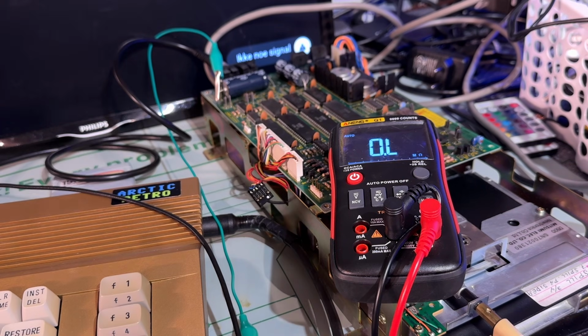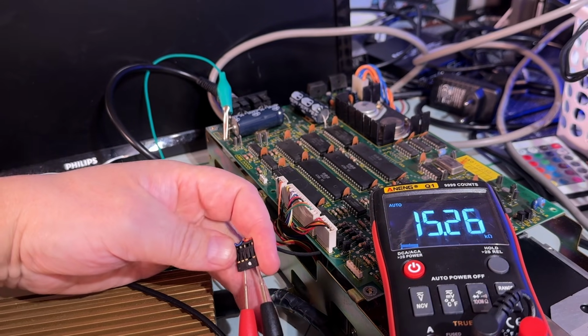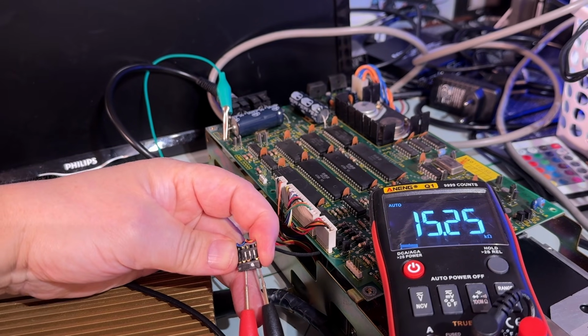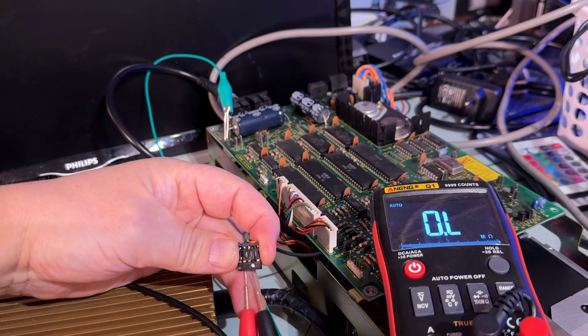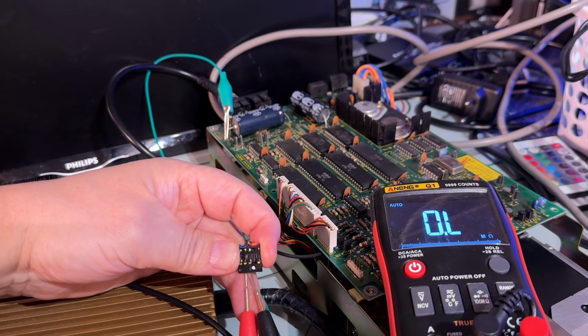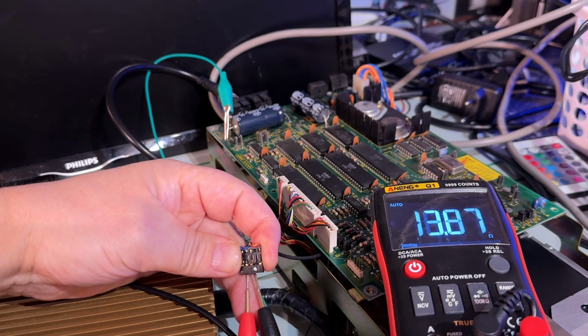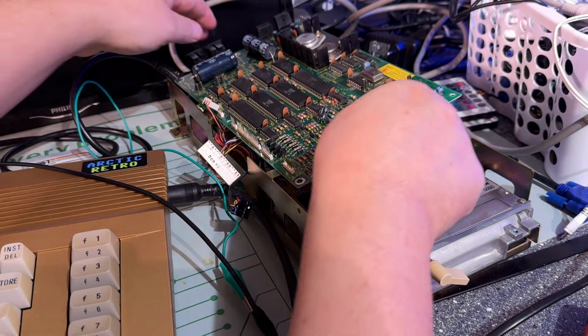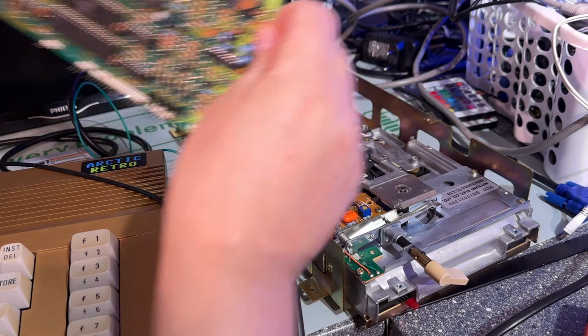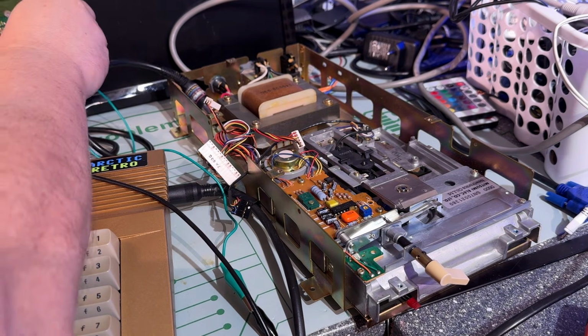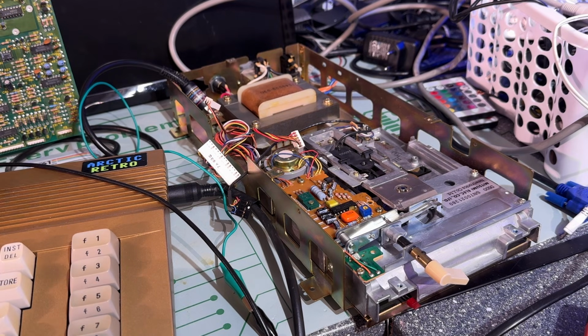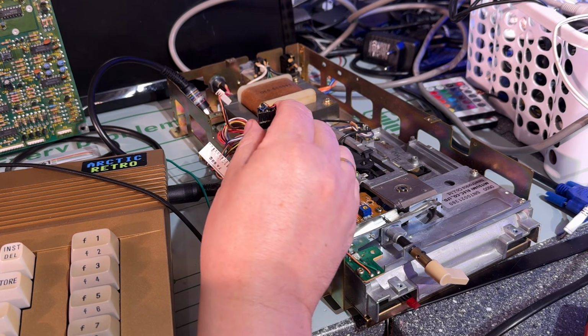So that means we have a faulty read-write head then. From the black wire, the center tap, to the red, there's 15 kilo ohms, but to the other it looks more normal, 14 ohms. If that's the case, then there's no way this can be repaired without a new head. But I'm not giving up quite yet — it could be a bad solder joint, or of course a bad cable too.